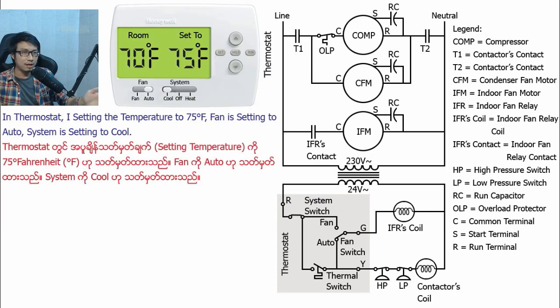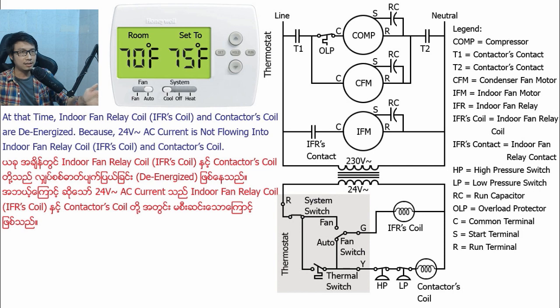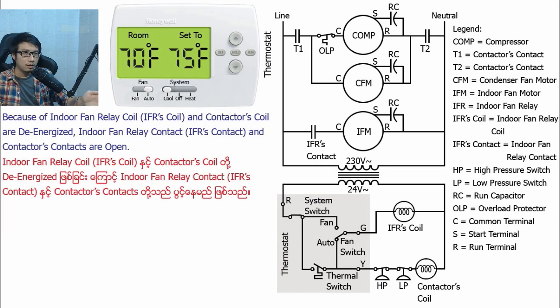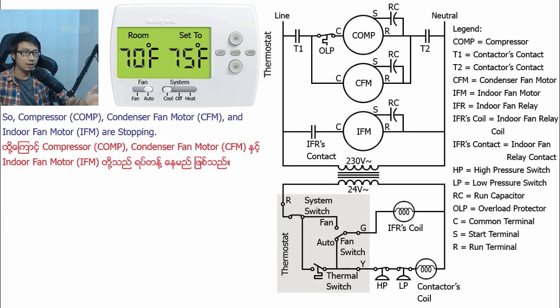In the thermostat, I set the temperature to 75 degrees Fahrenheit, fan is set to auto, and system is set to cool. In the wiring diagram, you will see the system switch is closed for cool, but the thermal switch in the thermostat is open because our set temperature is higher than room temperature. At that time, the indoor fan relay coil and contactor coil are de-energized because 24V AC current is not flowing into them, so the indoor fan relay contact and contactor contacts are open. Line and neutral current is not flowing into the compressor, condenser fan motor, and indoor fan motor, so they are all stopped.